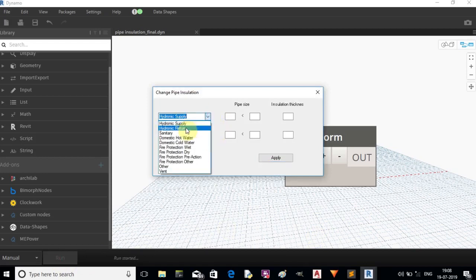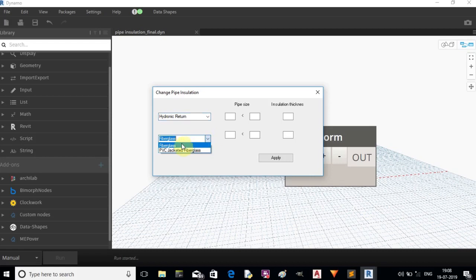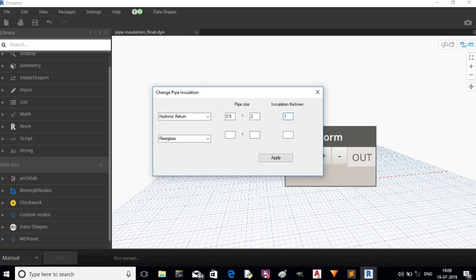Here I selected hydronic return pipes. In these two boxes I'll enter the pipe sizes. Half inch to two inch pipes shall be one inch insulation, and two and a half to four inch will be two inch insulation. Select the type of insulation and click the Apply button.